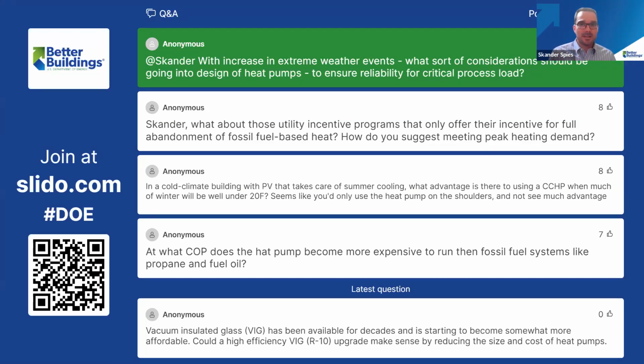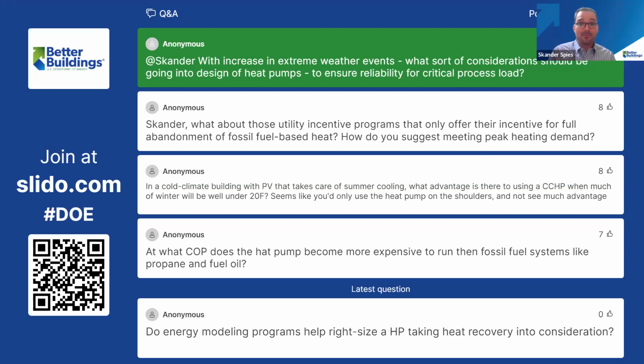What we're often designing on the heat pump system side is modular heat pumps, which Drake mentioned specifically, available from many manufacturers in many sizes, configurations, and applications. The power of those modular systems particularly is that you're not buying a single large piece of equipment—you're buying a series of smaller pieces of equipment that all work together in concert and can be serviced separately. So say your building needs 5 modules: if you have a specific concern about the reliability of that heat pump array, you might want to buy a 6th module, so you've always got 5 modules available to work and 1 that could be down for maintenance.